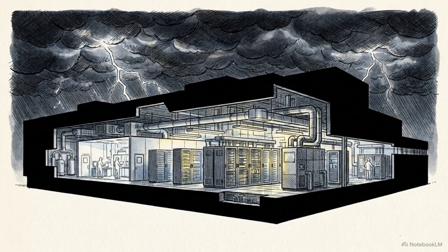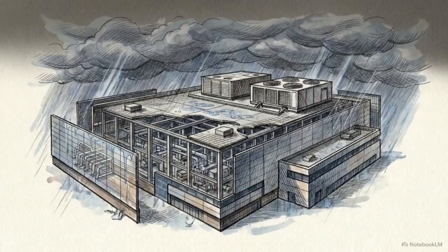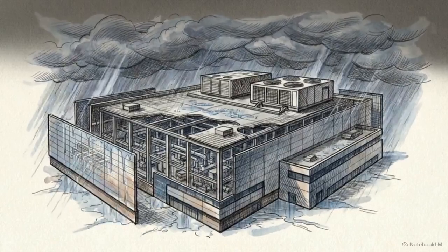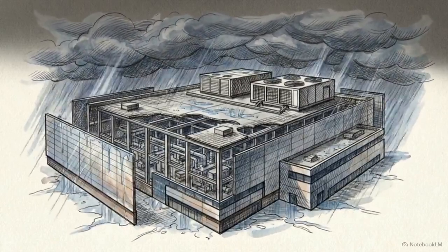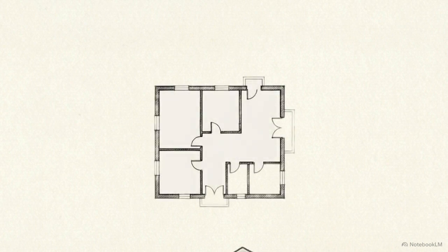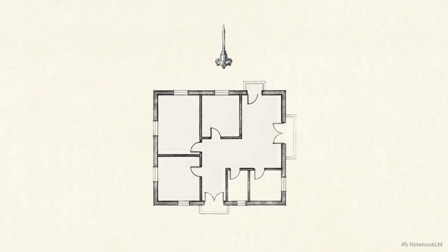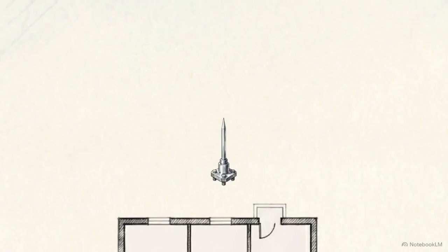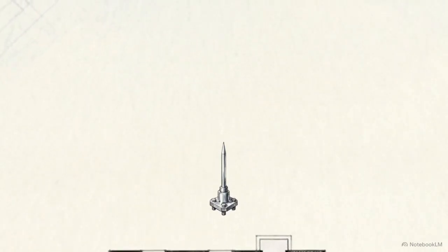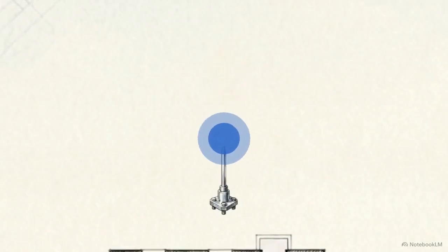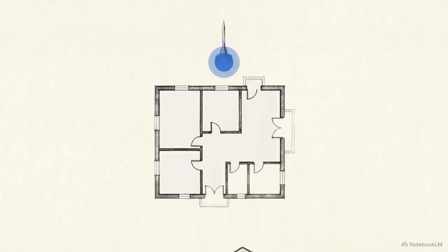Without these defenses, an afternoon thunderstorm can spark fires and destroy the sophisticated electronic systems that the factory needs to function. Let's look at how those defenses actually work when a heavy, violent storm rolls over our newly finished factory. This diagram shows our first line of defense in action. Right at the top, you will see a tall metal spike called an air rod, or lightning rod. Its job is to actively invite the lightning bolt to strike it, rather than letting the lightning find a random, vulnerable spot on the roof.